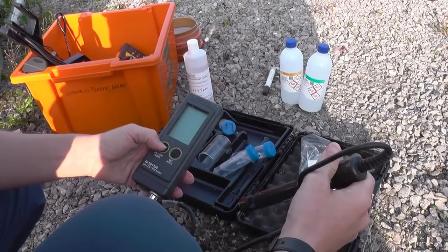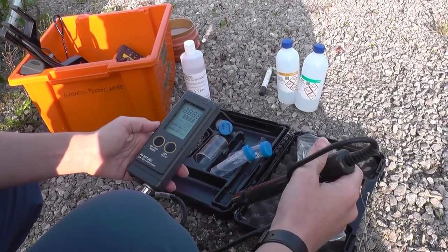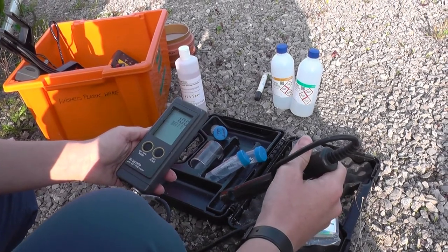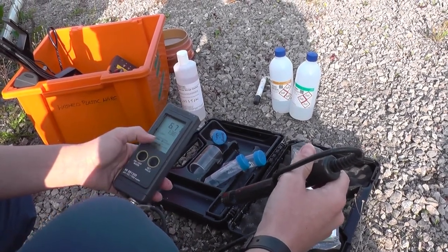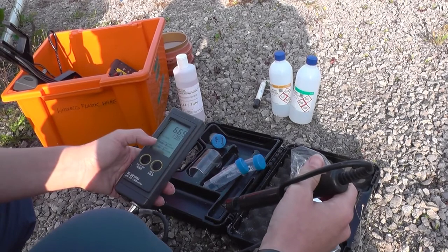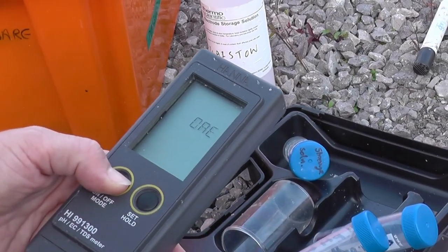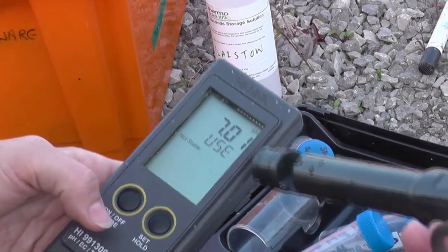So obviously we need to turn it on, so we press the on-off button, and then the screen will tell us what to do for calibration. So it says press calibrate, to calibrate press mode for 3 seconds, so that's what we do. First it pretends to go off, but if you keep pressing it, it goes to cal. So there we are. Now it wants to calibrate pH, it tells us in the top right corner.